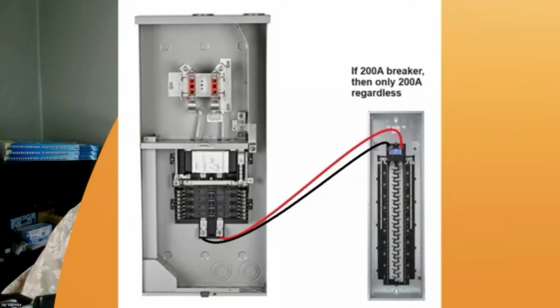Yeah, okay. Taylor is just putting in the comments, we've done 60 to 80 amps in outside load centers like that, and no derate is required. So at least in West Virginia, where Taylor is, the inspector has let him get away with it. And I think it's not a matter of getting away with anything. I think it's just logical that there shouldn't be that problem.